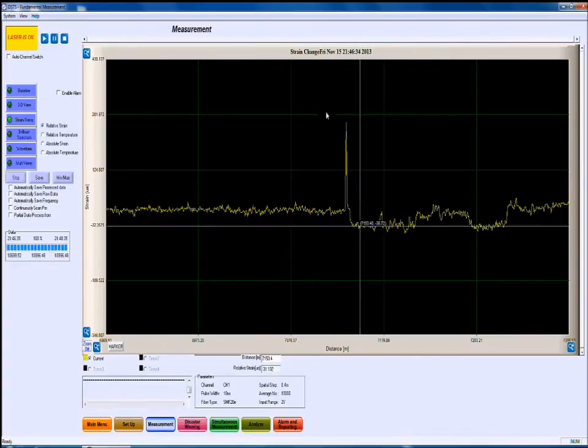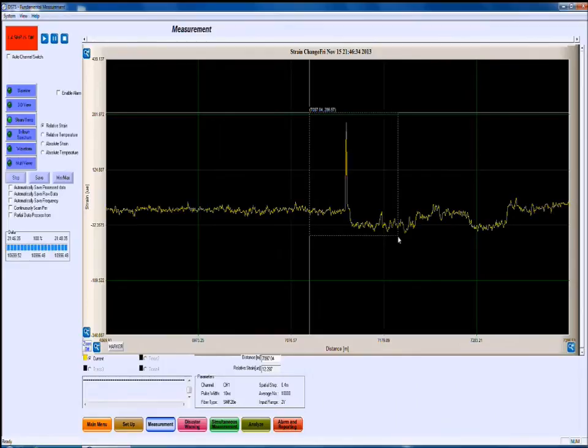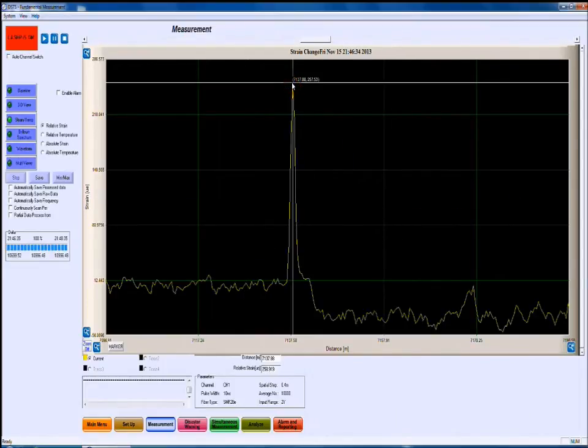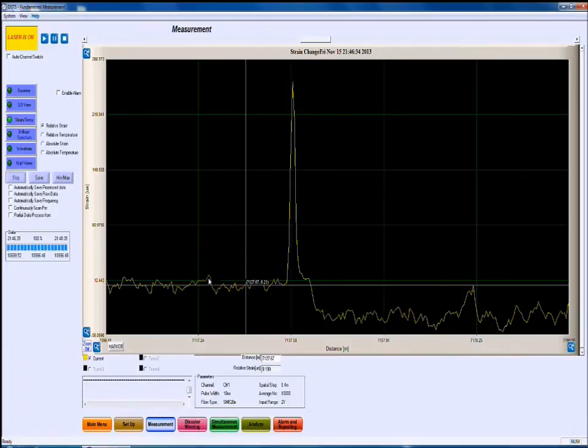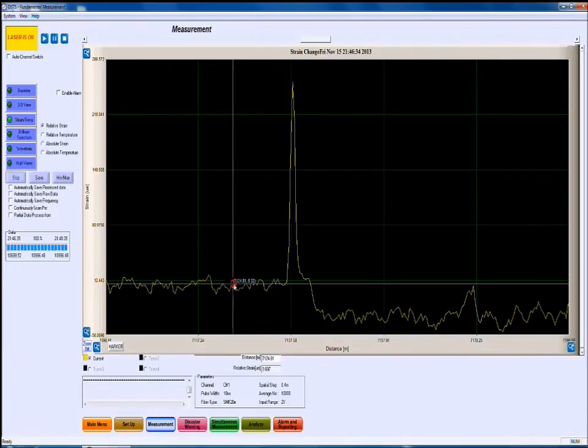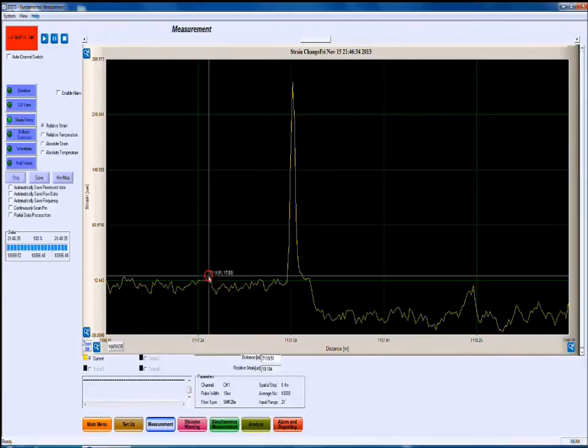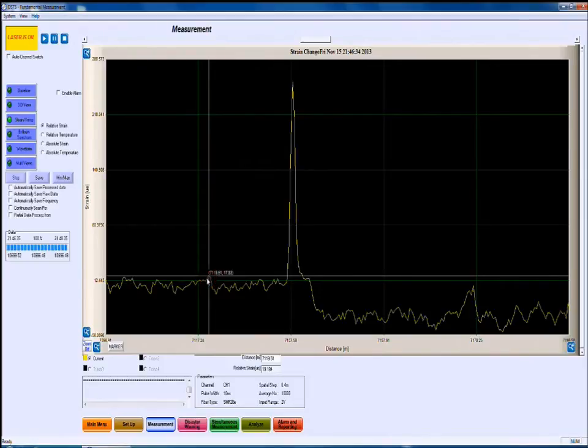It is still well above the background. And if we take a reading off it, it's about 257 microstrain, compared to a background level here of around less than 17 microstrain. So again, we have a signal here that's about 15 times as strong as what our background level is. Very easy to detect. Let's now disconnect our fiber from our Brillouin sensor and hook it up to our OTDR.